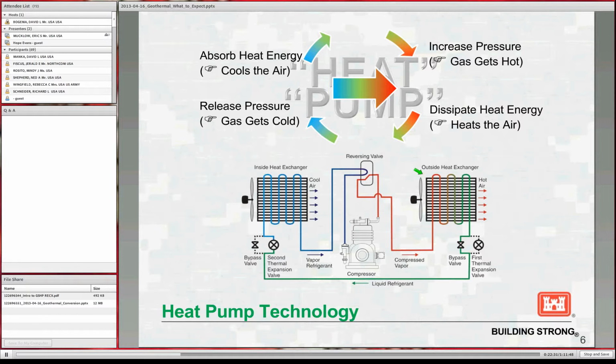So then the gas, as heat energy is transferred into the air stream, the ductwork, continues on, and of course it's cooled down a bit to maybe call it a medium temperature, and then it goes back out to that outside unit where it goes through one of these fancy valves that basically releases that high pressure. And by the laws of conservation of energy and the pressure and volume law, we know that when you release pressure, it's going to cool down. If you've ever had an aerosol can, like one of those spray air dusters or whatever, and you sprayed it a while for a long blast, you can feel the can getting cold in your hand, and that's basically the same kind of thing. So the energy that was dissipated a moment ago through the air blowing across the inside coil is now being absorbed out of the air and coming back into the cycle again.